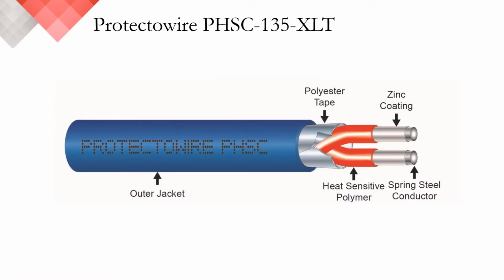Pictured here is our standard 135 degree Fahrenheit or 57 C detector, the PHSC 135 XLT. PHSC, as I just mentioned in the previous slide, stands for Protectowire Heat Sensitive Cable. This particular product uses two standard spring steel conductors and is a normally open resistive contact device compatible with any IDC or initiating device circuit.